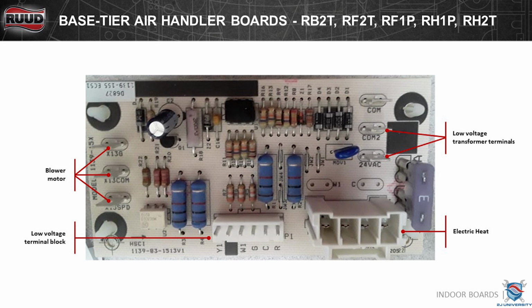So this is an air handler board here. This is your basic constant torque air handler board. You've got your electrical heat connections, still your 24 volts coming in, and then you have your speed taps for your blower on the left side of the board.